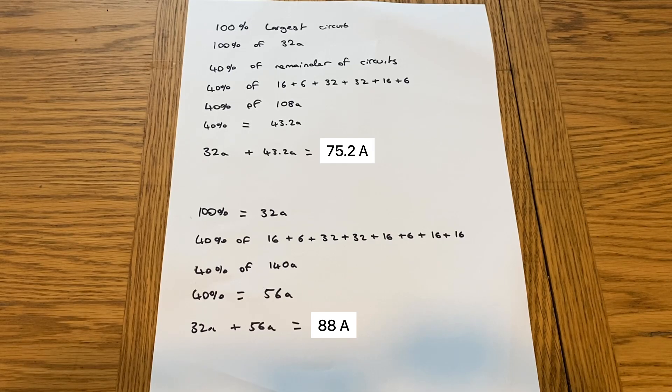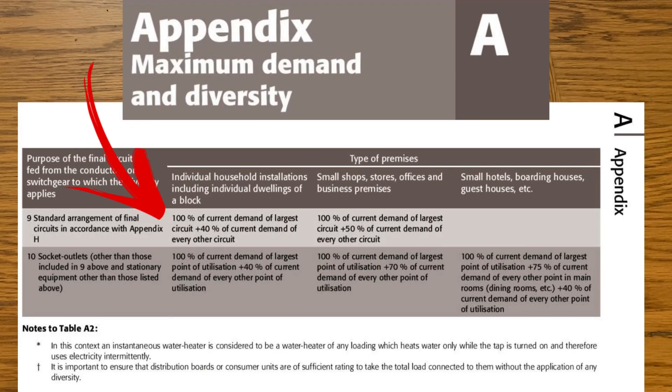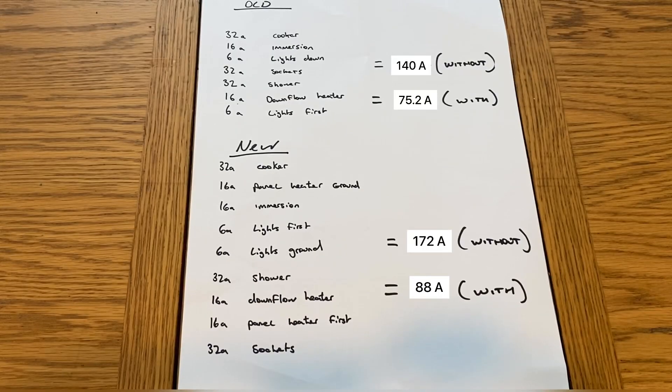We use this from the on-site guide and generally in a domestic dwelling we can do it this way as long as the circuit arrangements are in accordance with appendix H of the on-site guide. So now we've done our calculations with applying diversity, we can go back and look at the difference.